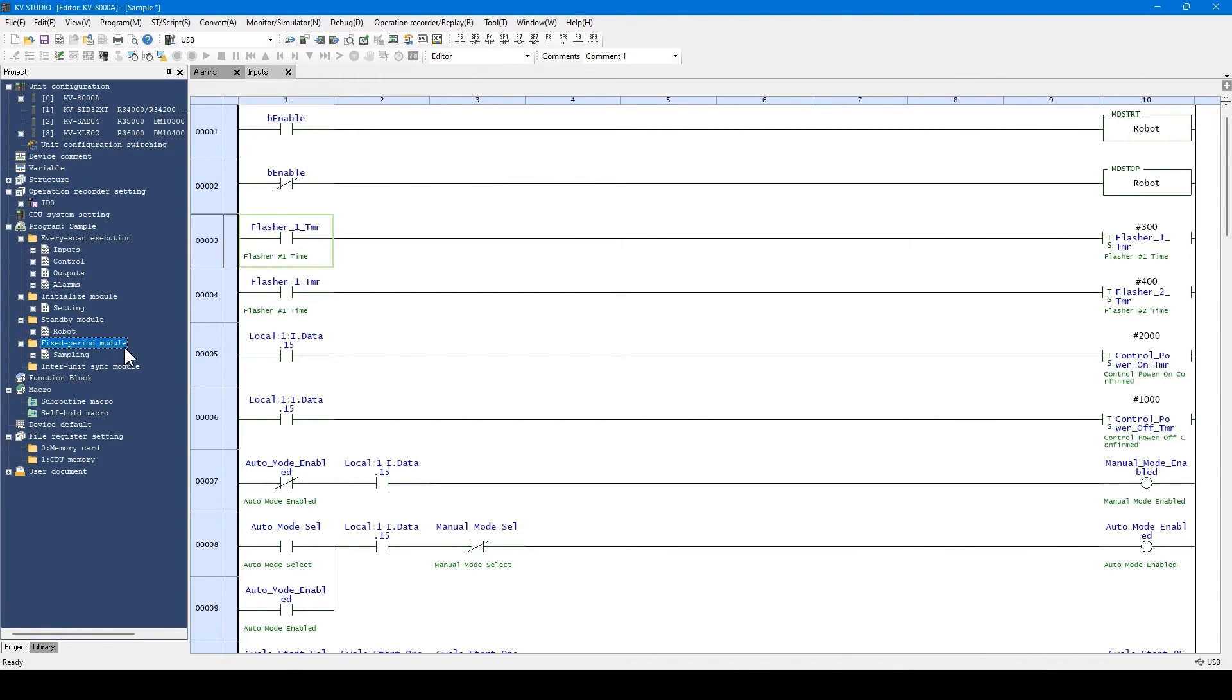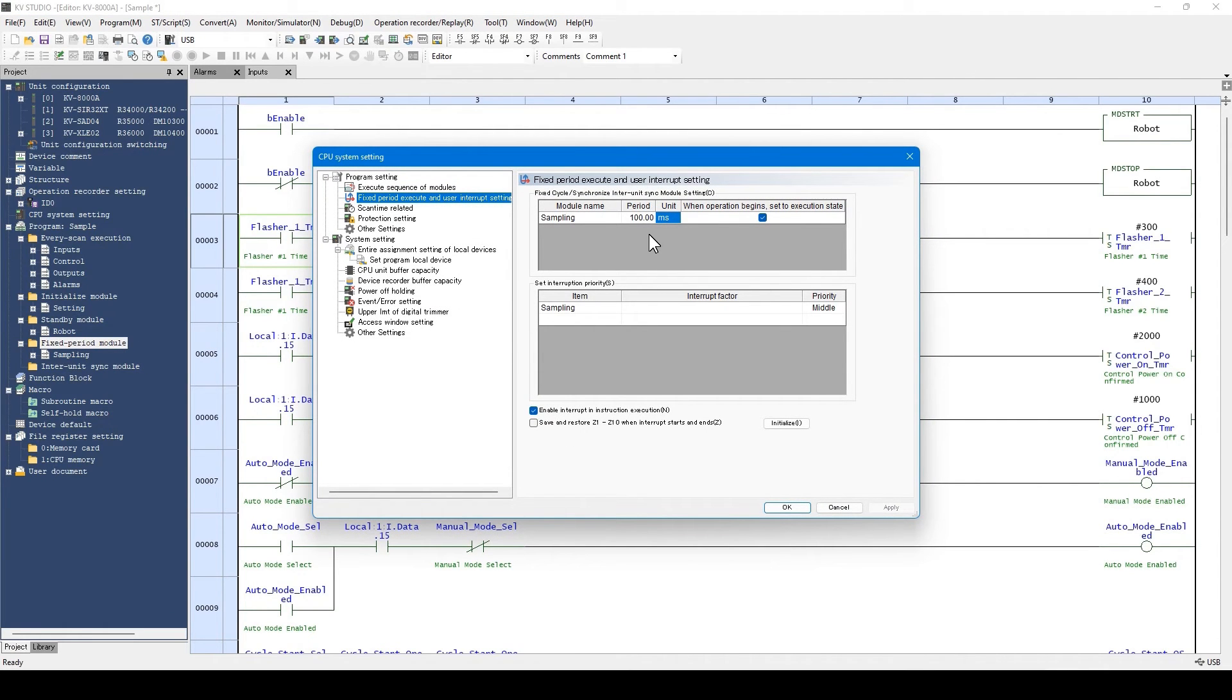Fixed period modules are modules which are executed in a preset interval. Up to four fixed period modules can be created for one project. The interval can be set by right-clicking and selecting the menu. The corresponding window opens. The available range for setting is from 50 microseconds to 60 seconds.